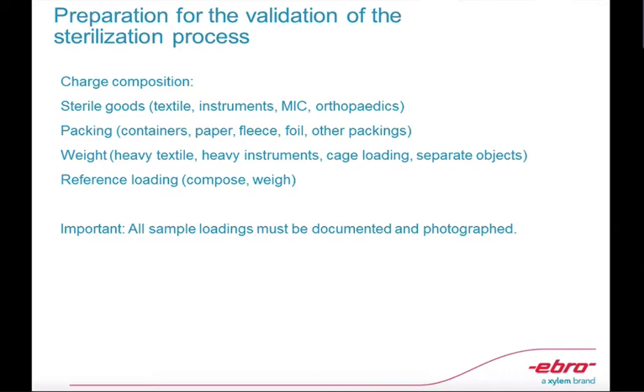These are the necessary preparations of the charge or batch composition. The software is very specific on charge numbers, but this is actually referring to batch numbers or lot numbers in other applications. Sterile goods, the packaging, the weight — which is very important for temperature equilibration conditions — and all sample loadings must be documented and photographed. This is how it is in CSSD units in hospitals, because everything must be properly documented.